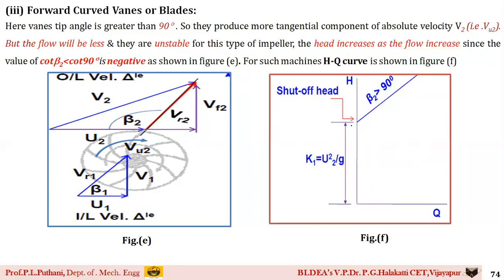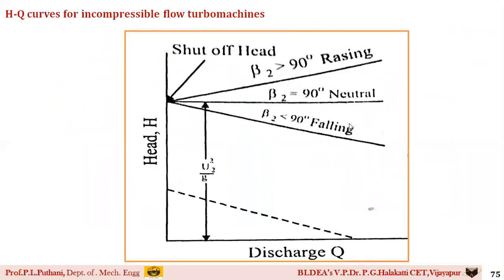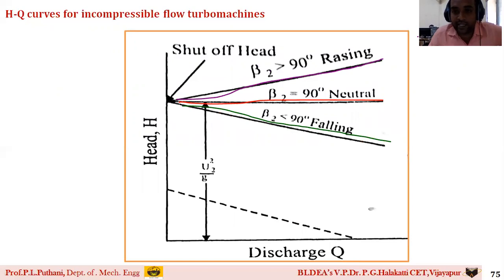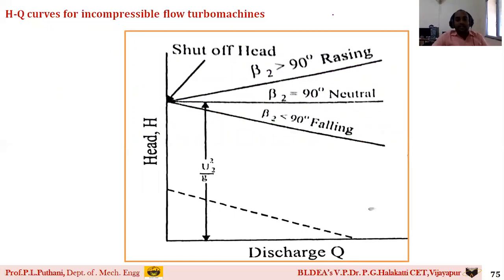Combining all three conditions on a single graph: for β₂ < 90°, head decreases as discharge increases; for β₂ = 90°, head remains constant (the neutral case); for β₂ > 90°, head increases with increasing discharge. These are the three performance curves for the three blade angle cases. In the next session, we will discuss key hints on how to draw velocity triangles under different conditions.